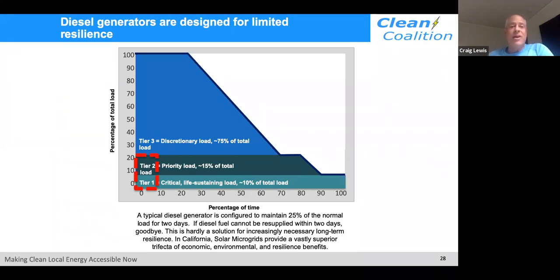They've got a lot of solar there but no energy storage yet. We did a study to map out how to build a community microgrid there to provide this level of resilience, meaning critical loads never turn off. So 10% of loads stay on forever, 15%—the tier 2 loads—stay on at least 80% of the time, and the remainder stay on about 25% of the time. If you have enough solar to net zero the site and add 2 hours of energy storage for every kilowatt of solar, this is the level of resilience you get.